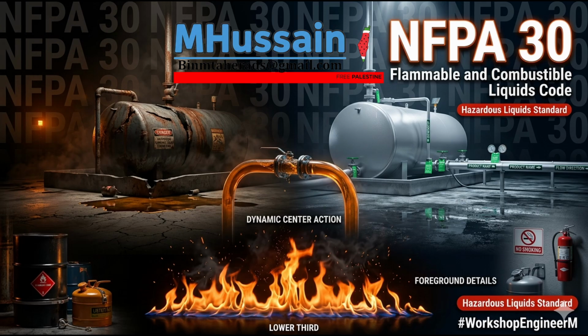Okay, then we have Class IB. Flash point is still below 73 degrees, so it's off-gassing at room temperature, but the boiling point is at or above 100. Slightly more stable against rapid boiling than IA, but still incredibly dangerous. And finally, Class IC. Flash point is at or above 73, but strictly below that 100-degree mark. And Class IC is insidious because it behaves totally differently depending on the season. Right, because of ambient temperature. Exactly. On a cool November morning, a spill of a Class IC liquid might not immediately create an explosive cloud, but if that exact same spill happens on a hot July afternoon in a poorly ventilated metal warehouse... It's actively pumping out an ignitable vapor blanket. Right. It really demands situational awareness from the operators.